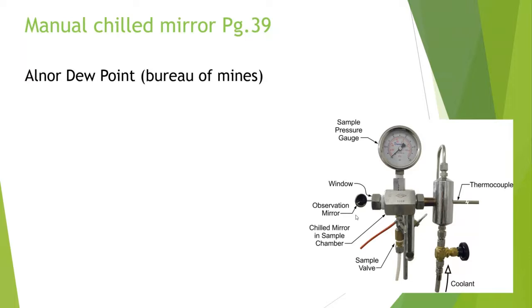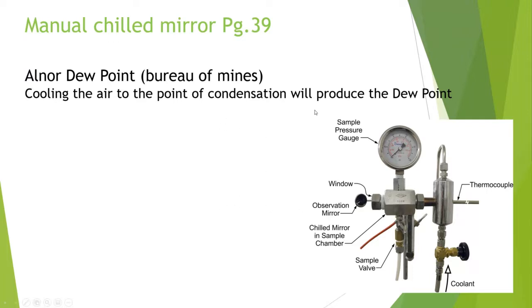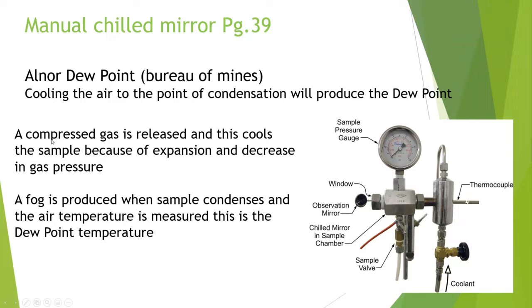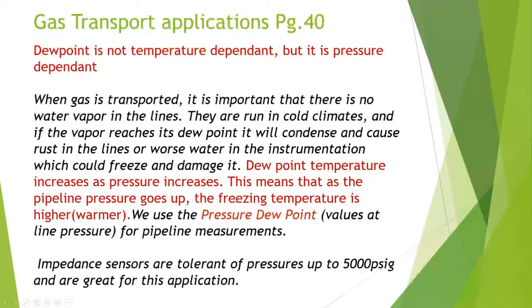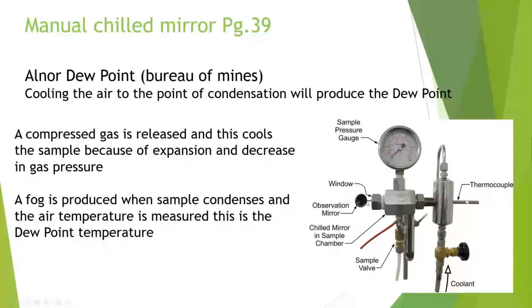The Alnor dew point or Bureau of Mines method is a manual version of the chilled mirror approach. Compressed gas is released, which cools the sample through expansion and a decrease in gas pressure — similar to an aerosol can getting cold when you press the nozzle. When the sample reaches its dew point, fog is produced. The temperature is measured on a thermometer or thermocouple at that moment to determine the dew point temperature.